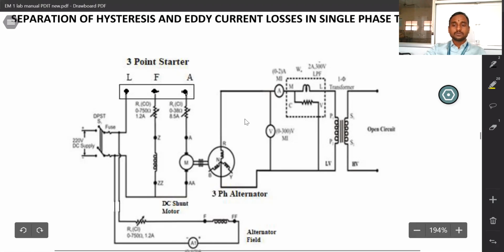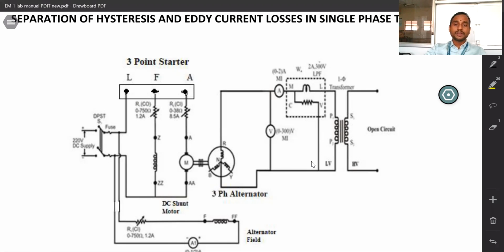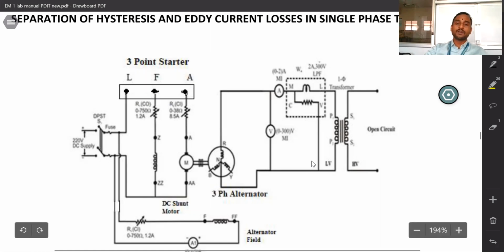power factor. In our experiment we have a multifunction meter. Instead of connecting all the 3 meters, we will connect a multifunction meter on the primary side of the transformer. Now, how to conduct the separation of hysteresis and eddy current loss, which can be derived from iron losses? For that purpose, we require a variable frequency, which can be achieved by a motor and alternator arrangement.